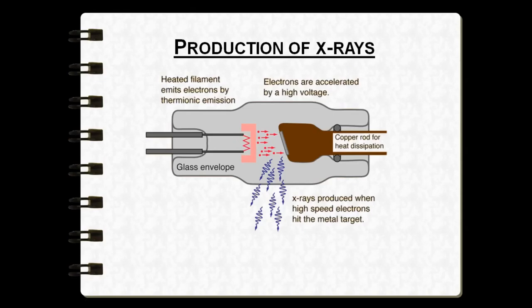Now we will discuss how x-rays are produced. Once the x-ray machine is turned on, electric current moves to the control panel and is directed to the tube head through electrical wires in the extension arm. This current is directed towards the filament in the cathode with the help of a step-down transformer, which converts the line voltage of 110 to 220 volts down to 3 to 5 volts to heat the tungsten filament.